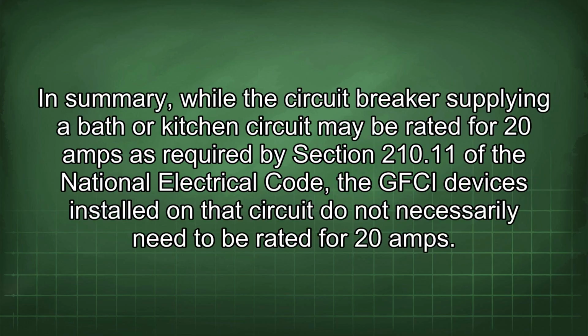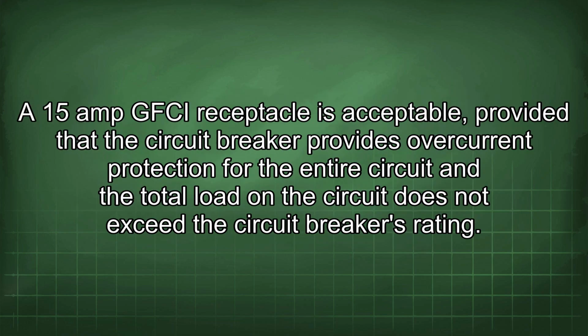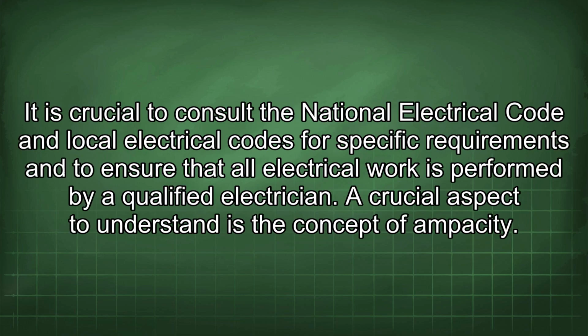In summary, while the circuit breaker supplying a bath or kitchen circuit may be rated for 20 amps as required by section 210.11 of the National Electrical Code, the GFCI devices installed on that circuit do not necessarily need to be rated for 20 amps. A 15-amp GFCI receptacle is acceptable, provided that the circuit breaker provides overcurrent protection for the entire circuit and the total load in the circuit does not exceed the circuit breaker's rating. It is crucial to consult the National Electrical Code and local electrical codes for specific requirements and to ensure that all electrical work is performed by a qualified electrician.